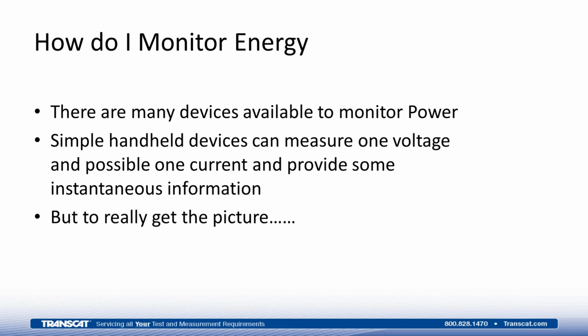Now, there are many different types of devices available in the industry to monitor and do this kind of measurement. The simplest devices you're going to run into are handheld devices, which could be used to measure one voltage and possibly one current. These might be like a multimeter, capable of measuring the voltage. You could put the two leads across a phase, and you'd be looking at the instantaneous voltage being provided to a load. Some of those devices allow you to add an option, which is a current probe. By attaching the current probe to the meter, you could put the probe around the conductor and monitor the current flowing to the load. In both of these cases, these are instantaneous values.